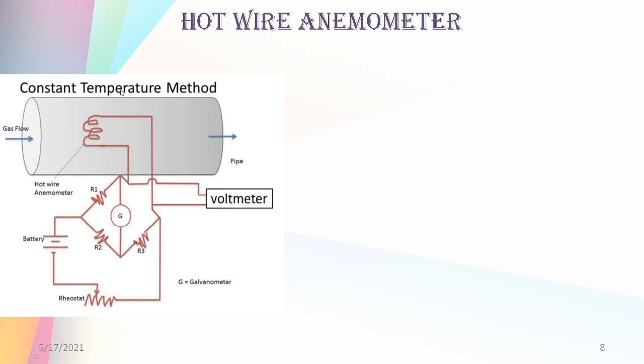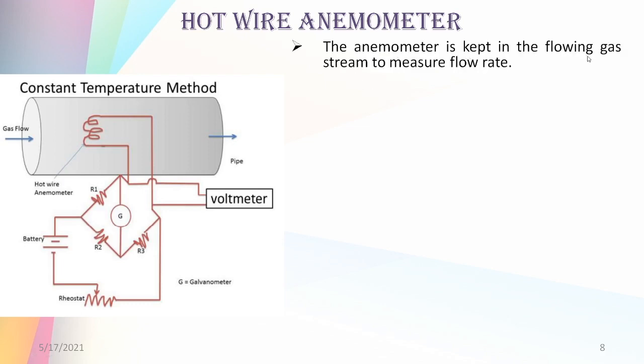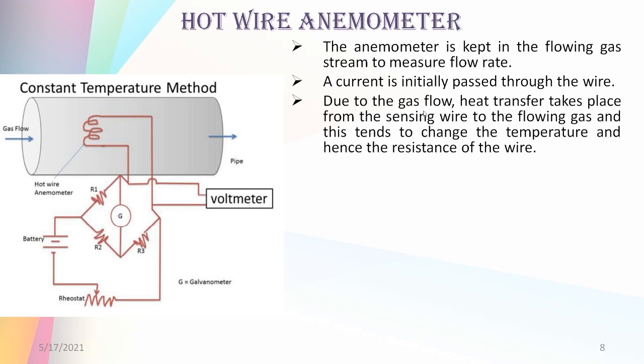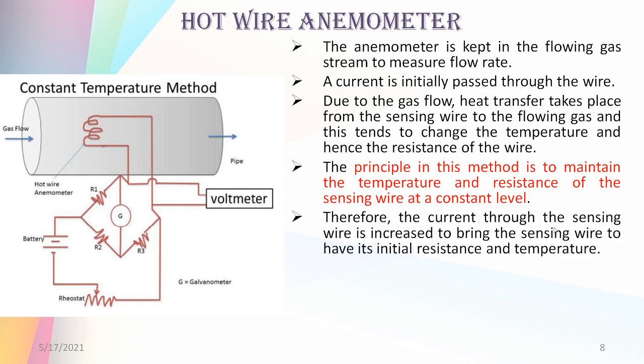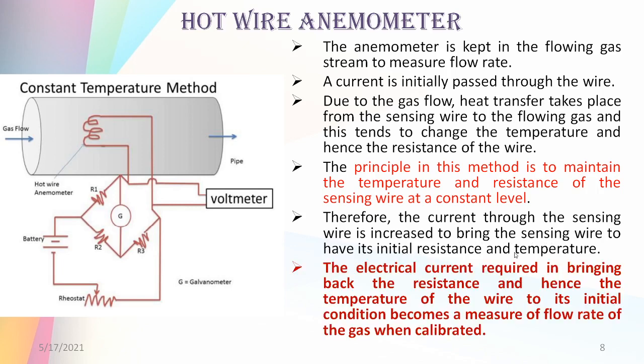In the constant temperature method, the current is varied to maintain the temperature and resistance of the sensing wire at a constant level. Due to gas flow, heat transfer takes place from the sensing wire to the flowing gas, which tends to change the temperature and hence the resistance of the wire. The current through the sensing wire is then increased to bring the wire back to its initial condition. The electrical current required to bring the resistance and temperature of the wire back to its initial condition becomes a measure of the flow rate of the gas when calibrated.